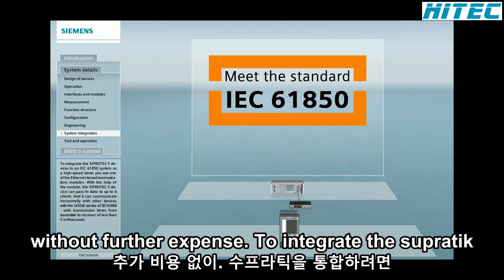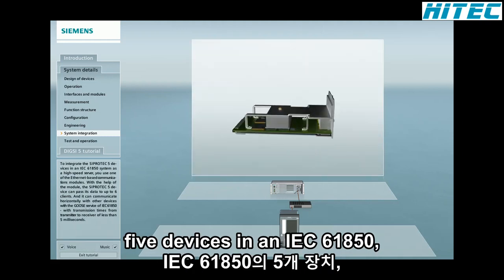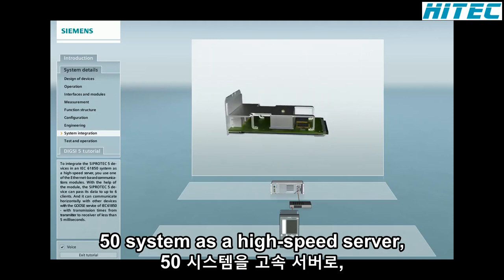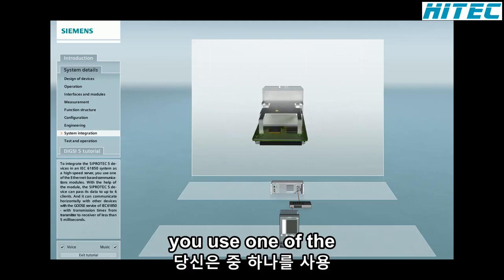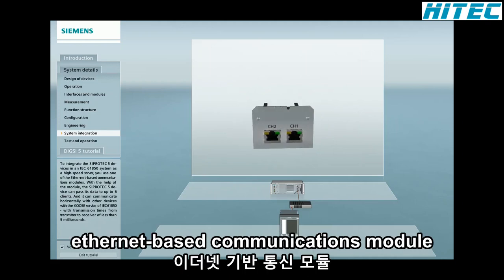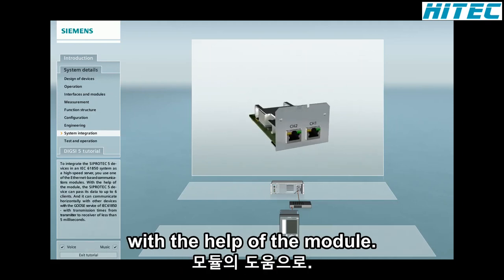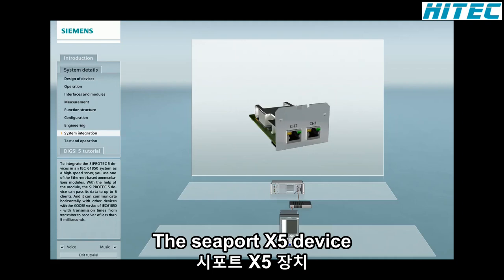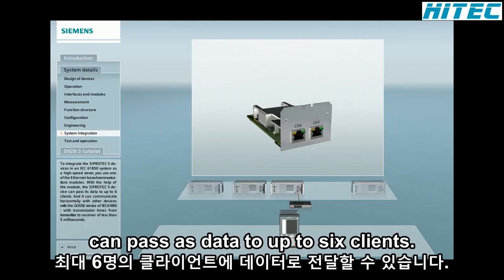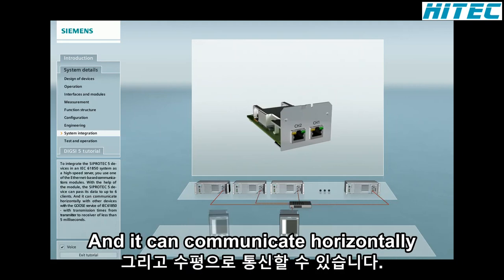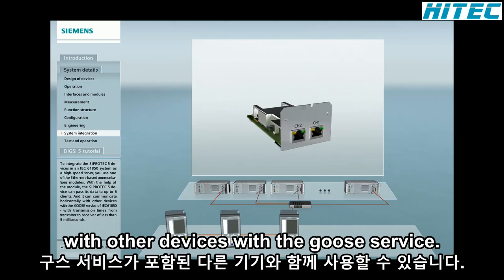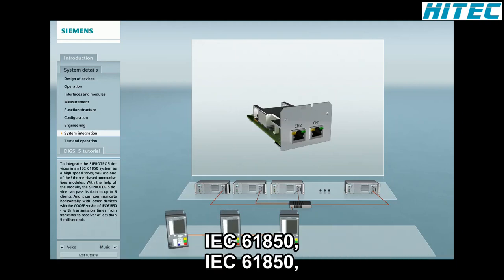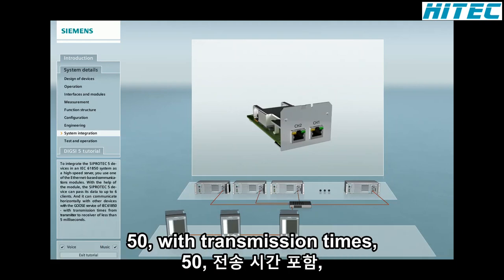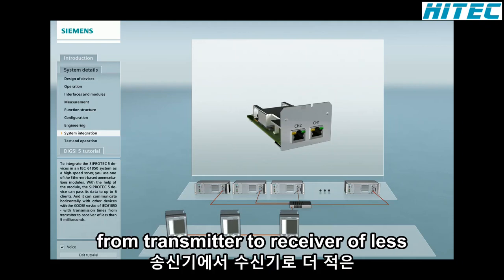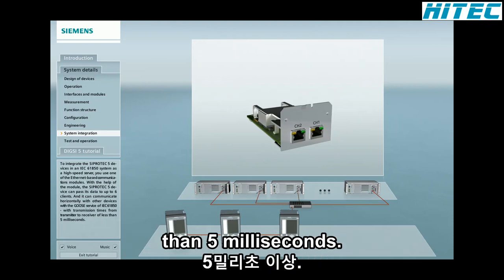To integrate the SIPROTEC 5 devices in an IEC 61850 system as a high-speed server, you use one of the Ethernet-based communications modules. With the help of the module, the SIPROTEC 5 device can pass its data to up to 6 clients. And it can communicate horizontally with other devices with the GOOSE service of IEC 61850 with transmission times from transmitter to receiver of less than 5 milliseconds.